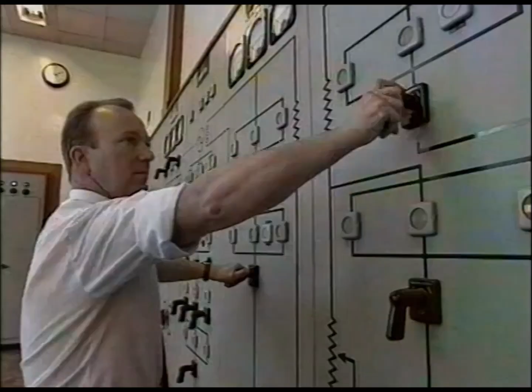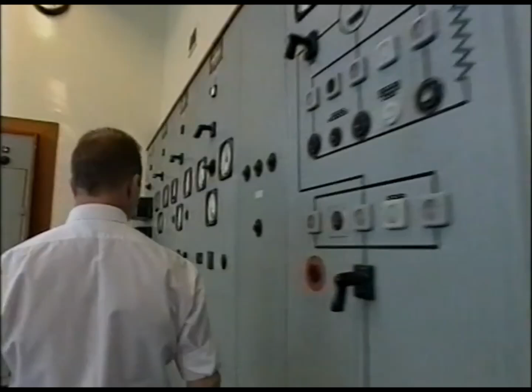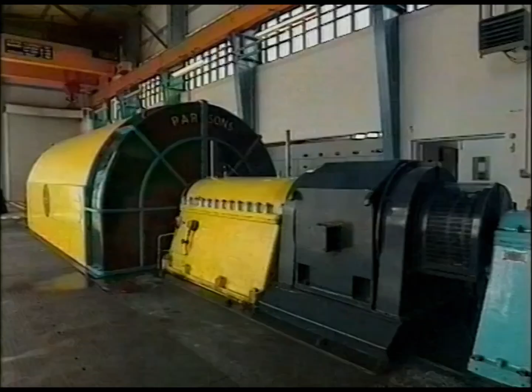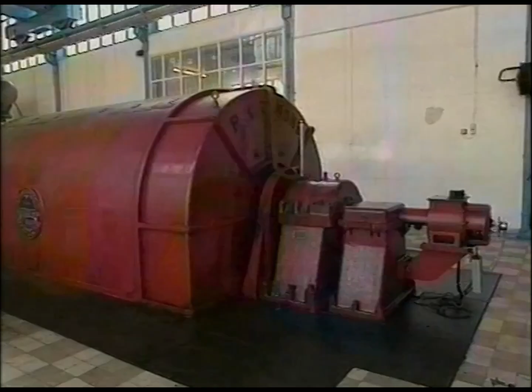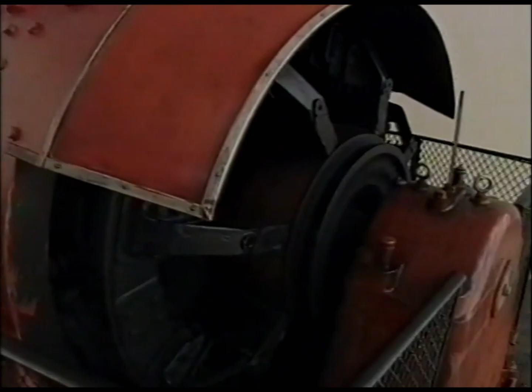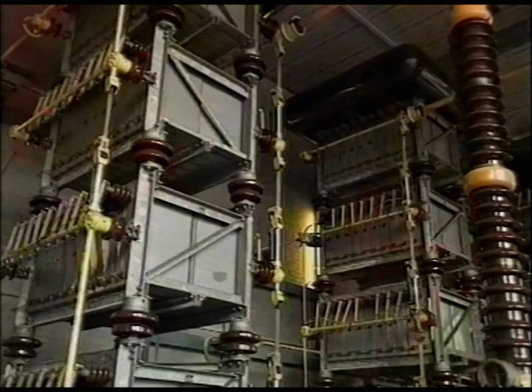This is the nerve centre of the British short-circuit testing station, a sophisticated control room kept entirely apart from the rest of the Reyrolle operation as part of that overriding commitment to confidentiality. This laboratory can call on 3 separate power sources for its test. 2 purpose-built short-circuit generators deliver direct test energy after their driving motors have been disconnected. The generators have a combined short-circuit output of 3,700 MVA. In addition, a 600 kilojoules capacitor bank can be used to make synthetic tests to the highest rating.